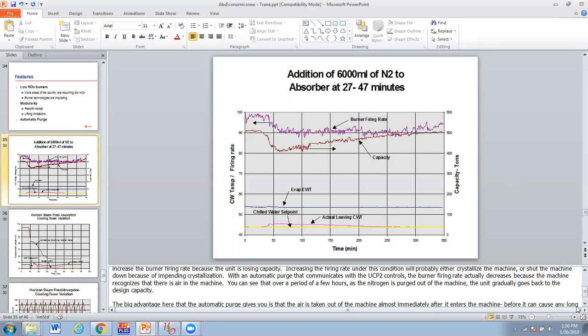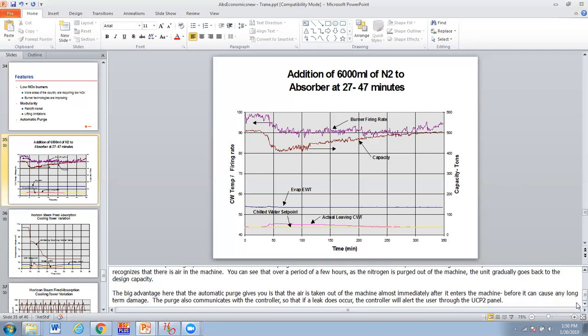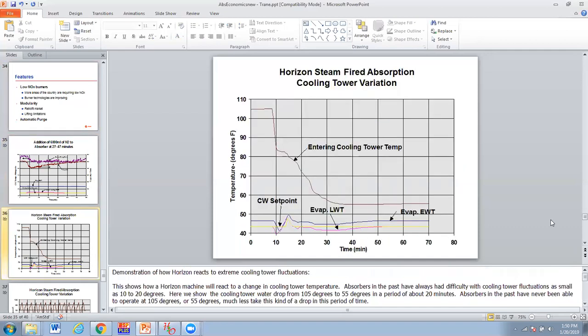The big advantage the automatic purge gives you is that the air is taken out of the machine almost immediately after it enters, before it can cause any long-term damage. The purge also communicates with the controller, so that if a leak does occur, the controller will alert the user through the control panel. So pretty good. Okay, so that's the purge controls.